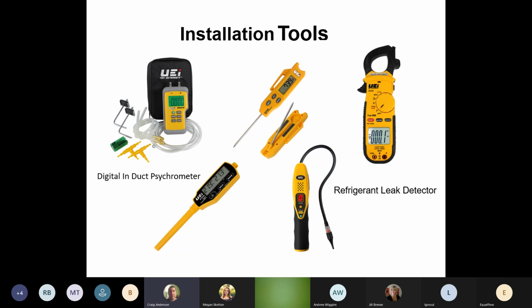Other tools, manometers. You're going to need these, whether it's in heating or cooling. We need to start checking static pressure more frequently because we're dealing with ECM motors. Pocket thermometers, always have two, so you can check your return and your supply at the same time. You're not bouncing back and forth. It's going to cut a lot of time off if you have two. A nice multimeter clamp on so we can check amperage. Refrigerant leak detector. Not everybody needs one in their truck. It's great to have one in the company if you have one of those leaks that are hard to find. Digital psychrometer. Do your wet bulb, dry bulb in the house. Great little tool. They're pocket size now too as well.